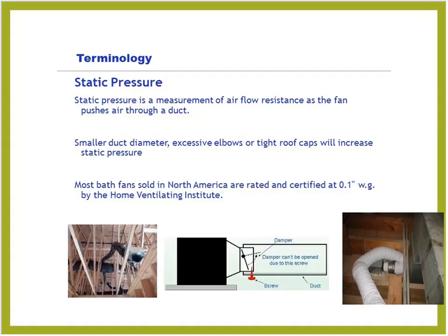And then you've all probably seen the picture on the left. Yes, we want to ventilate. We want to duct our fans to the outside, and we don't want terminations to the front of the building. So often they get run to the back of the building, but draping them over trusses can create pinch points, especially if you get water weight in there from condensation, and can create significant static pressure as well. So we want to do everything we can to minimize elbows and whatnot, and get rid of that static pressure that really does kill performance of a piece of ventilation equipment.